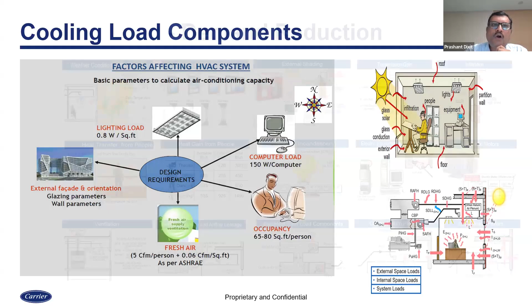So what does this cooling load comprise of? Mainly three parameters: external, internal, and system related challenges. External is anything beyond your control - weather conditions affecting the building, dry bulb, wet bulb, humidity, window and glazing types, shading coefficient, transmission gains, infiltration - all this can be external.